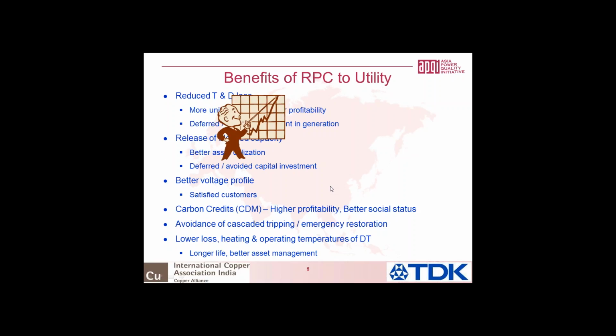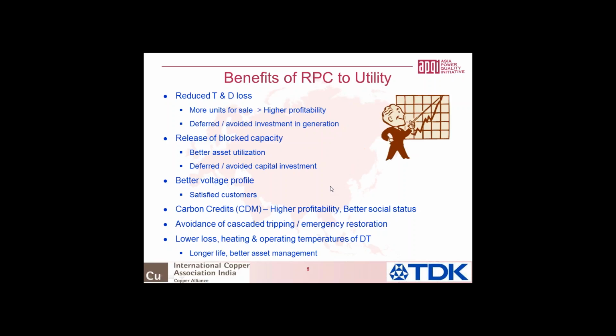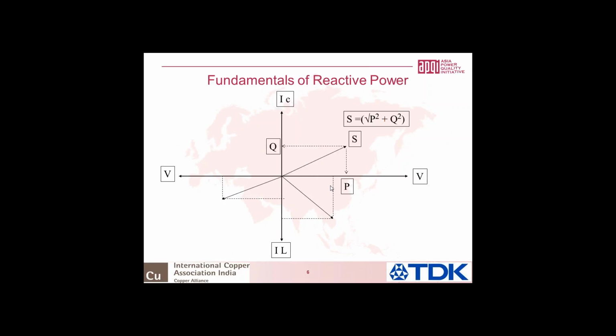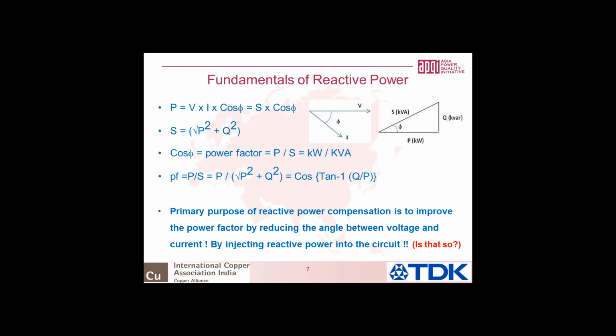Now let's change gears and look at the fundamentals of reactive power before we talk about reactive power compensation in a harmonic environment. This is a classical quadrangle where you have a voltage axis, you have a current axis which could be at any angle to the voltage axis depending on whether it's an inductive load, resistive load, or a capacitive load. Now let's move on to the next slide, and you have the classical equations. We know that the real power designated with the letter P is the product of voltage into current, volt-ampere, into power factor, which is cos phi, where phi is the angle between the voltage wave and the current wave.